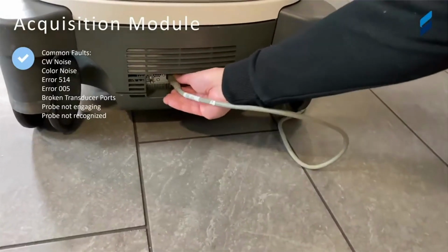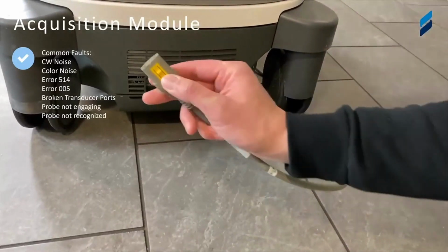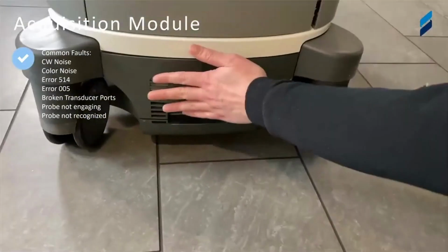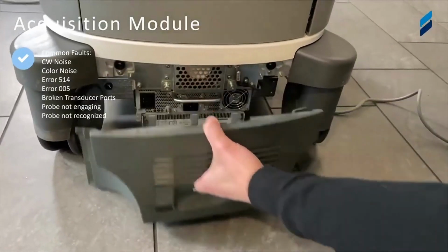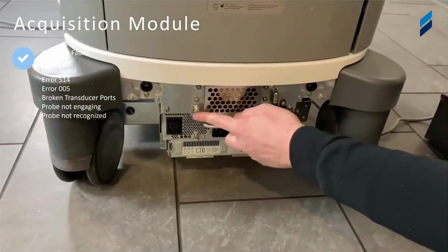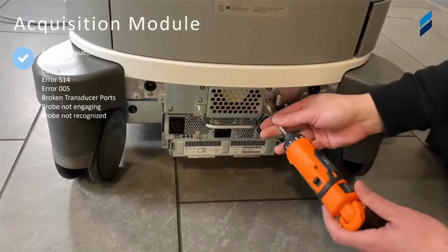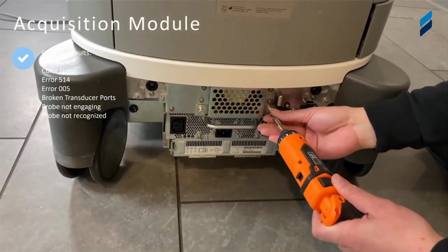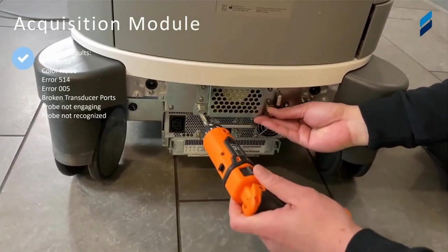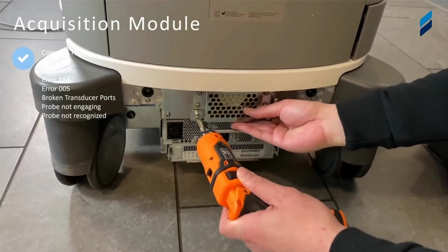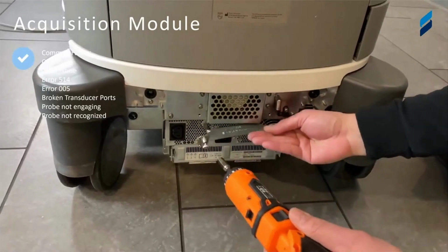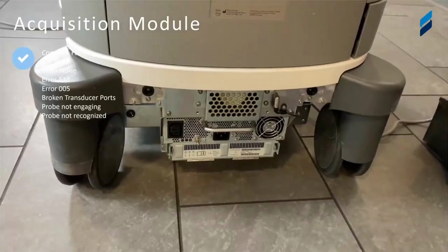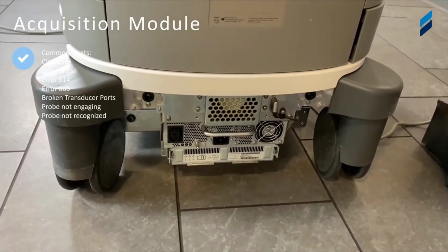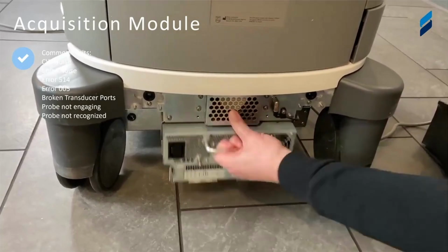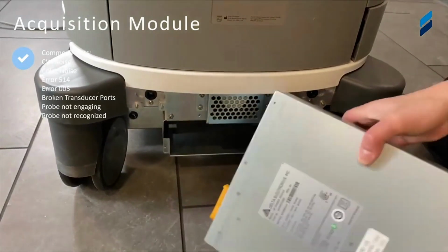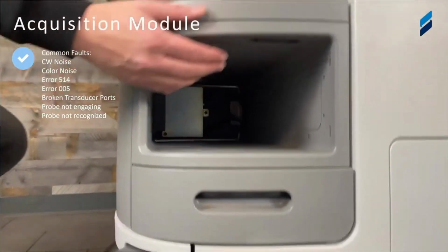We're going to start off with the acquisition module. This is the most common failing part in the machine, as we talked about before. The most common faults here, CW noise and color noise, like we talked about. You'll get some hard error code faults, 514, 005. Also included is our broken transducer ports, which do happen, or probes not engaging or probes not recognized because there's something faulty in the probe identification circuits that are on there.